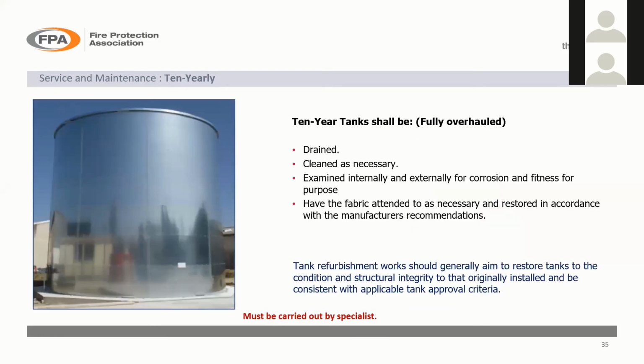This is the 10-year, talked about 3 years. After 10 years, your 10-year tank needs to be fully overhauled. It needs to be drained, cleaned as necessary. It needs to be examined internally and externally for corrosion. And the idea is that a tank refurbishment work should generally aim to restore the tank to the condition and structural integrity that it was installed to originally.